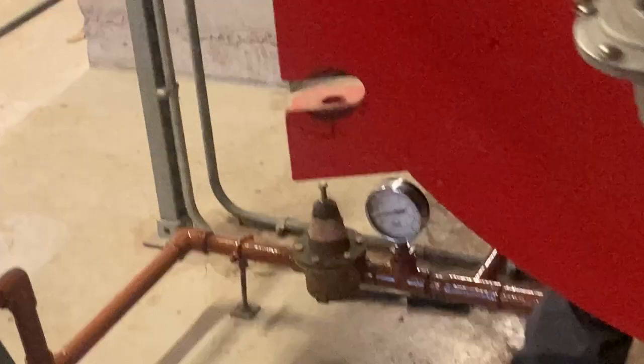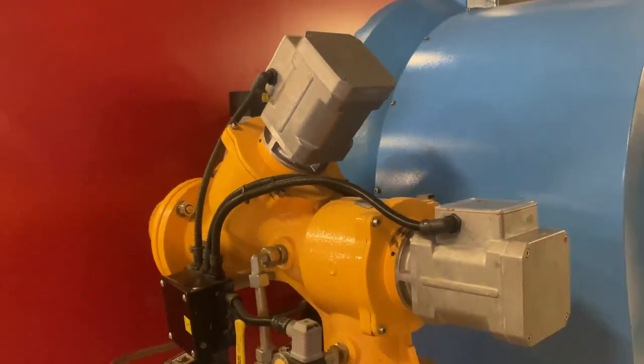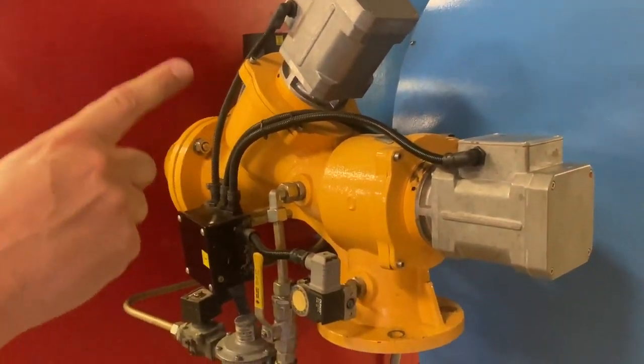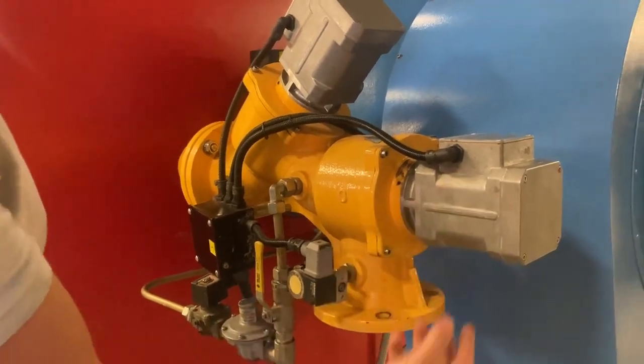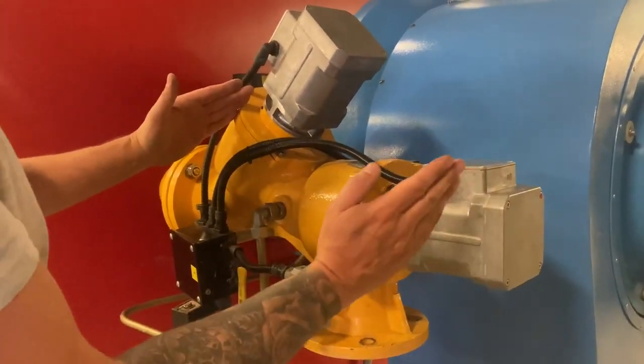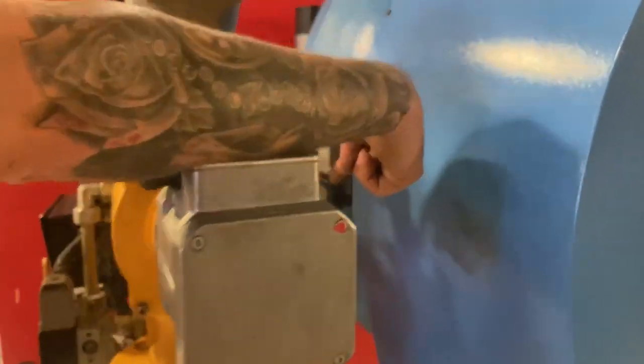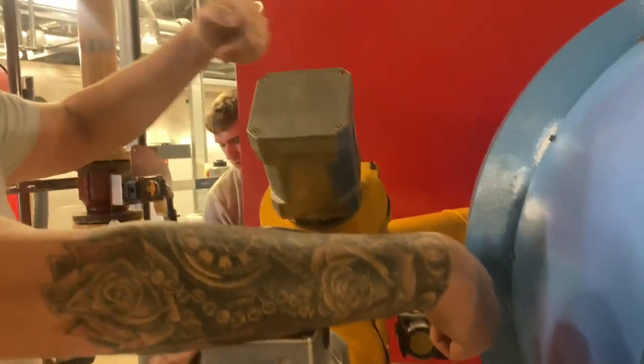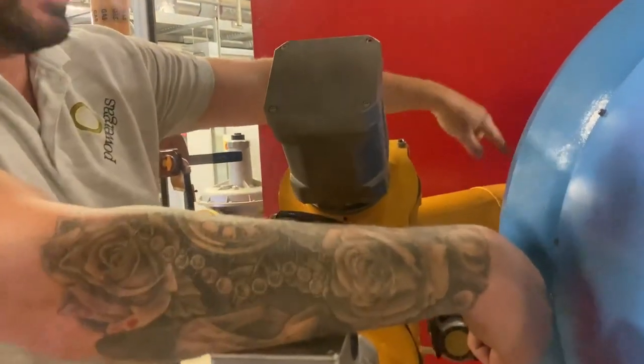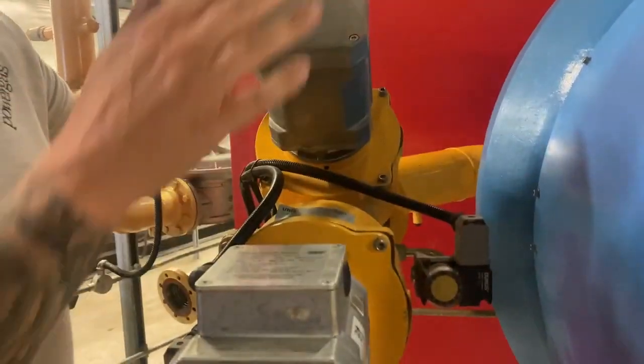so when this is connected up, gas comes in there, you've got a gas valve and a gas valve, and all they do is open and close. And they will gas prove that they are working. Initially, gas will come in there, that will open, gas will come into that chamber there, that one will close. That pressure switch there will then determine whether this one is working correctly, because if that seal's gone, that pressure will drop because the gas will leak into the combustion chamber. So that's how it proves that it's gas soundness tested.